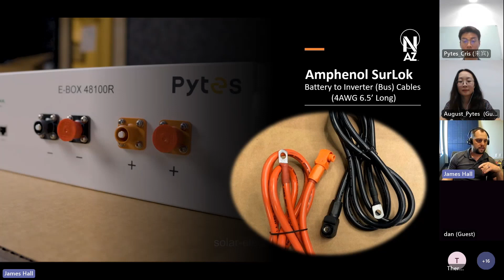We can take those battery to battery cables and parallel 2 batteries together, then carry 100 amps on the main bus cable up to a common battery bus. If you're doing 4 batteries, you'd typically get 2 battery to bus cables and use the battery to battery cables to parallel your batteries. That allows you to carry 200 amps continuous current with just 2 pairs of cables.